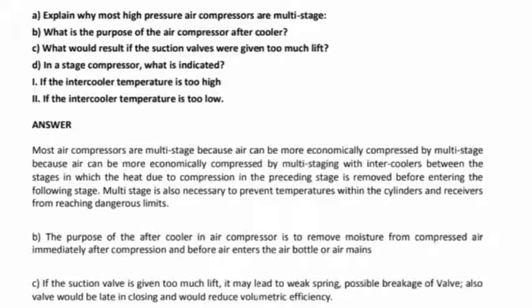Most high-pressure air compressors are multi-stage because air can be more economically compressed by multi-staging, with intercoolers between the stages in which the heat due to compression in the preceding stage is removed before entering the next stage.